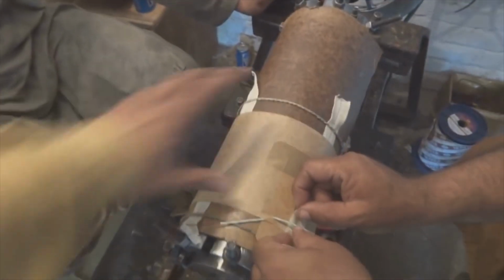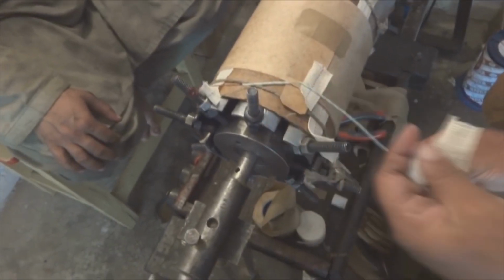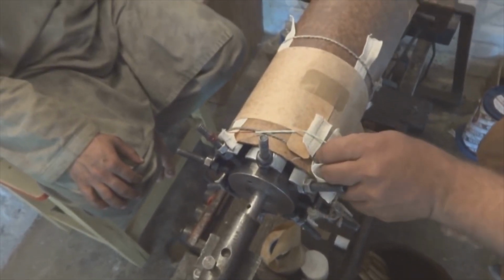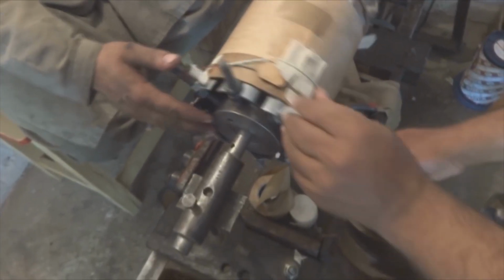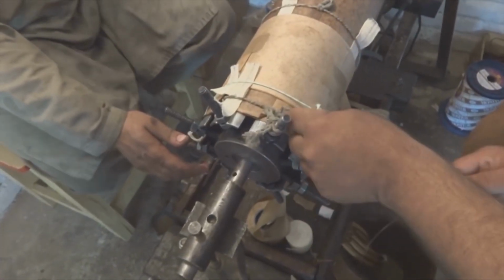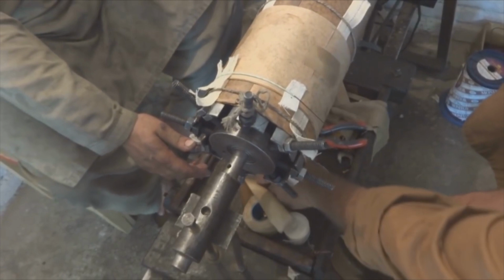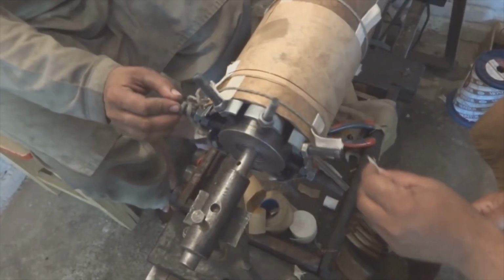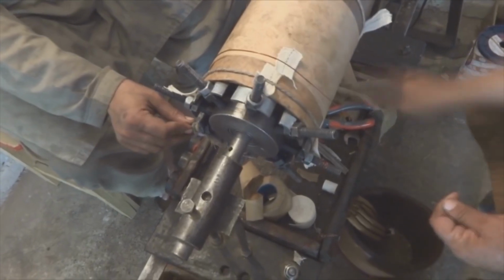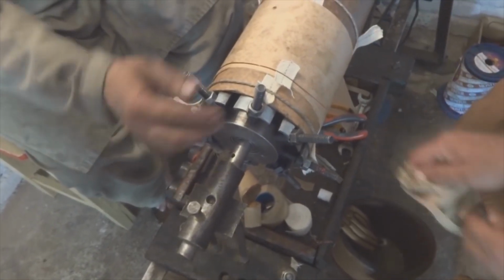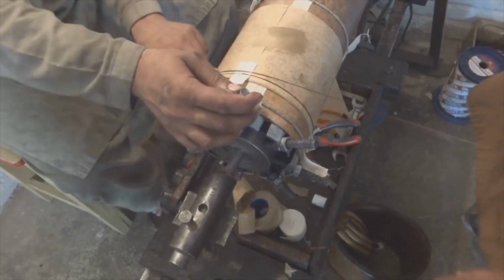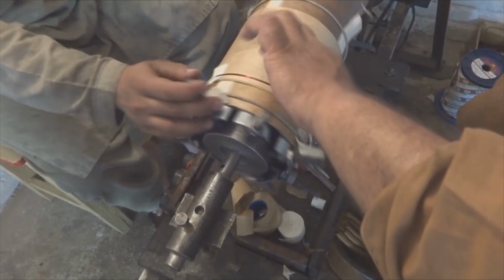The starting of the winding has been put in, and here you can see some sleeving insulation they have provided at the start, and later they provide some cotton tape pieces. These cotton tape pieces are actually to hold the winding. This starting of the winding must be held, because if it is not held, the winding can come out due to centrifugal forces, and that will be a problem. So that's why they keep these small pieces of cotton insulation tape, so that the windings will not come off.